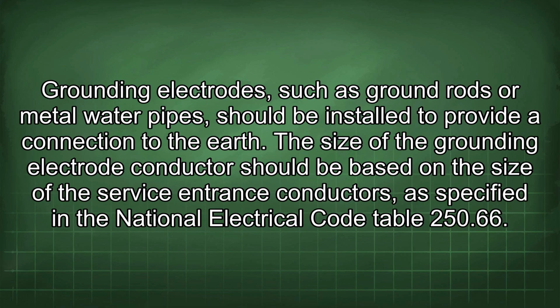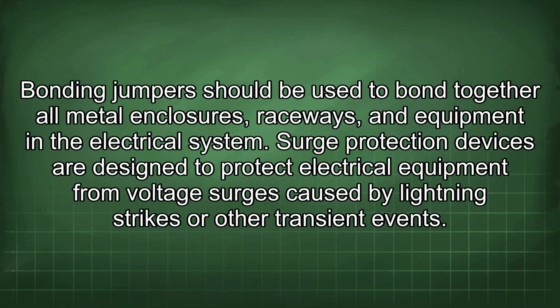Grounding electrodes, such as ground rods or metal water pipes, should be installed to provide a connection to the earth. The size of the grounding electrode conductor should be based on the size of the service entrance conductors, as specified in the National Electrical Code Table 250.66. Bonding jumpers should be used to bond together all metal enclosures, raceways, and equipment in the electrical system.